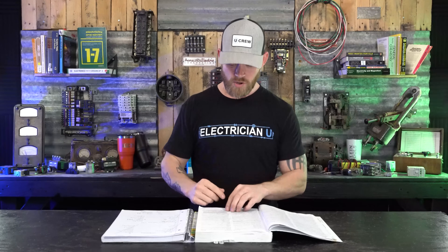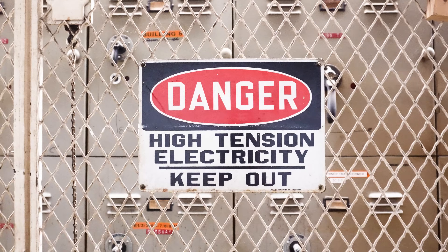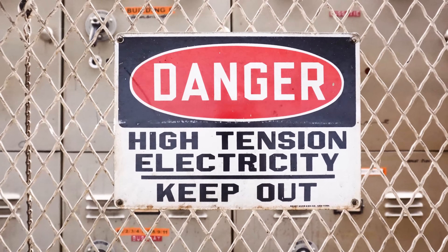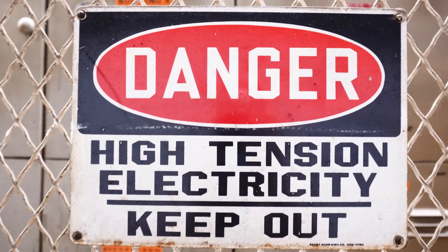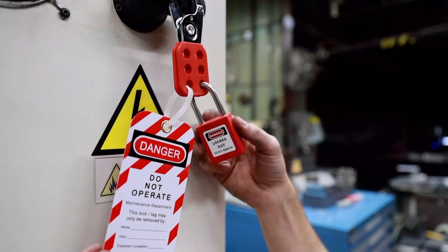Next up is 'enclosed.' There's a difference between concealed and enclosed, and this is where the confusion comes in. Enclosed means surrounded by a case, housing, fence, or walls that prevent a person from accidentally contacting energized parts. It might be an area of electrical equipment someone can't enter, or it might be an enclosure like a box with a cover that you could put a lock on — something that prevents people from touching live parts inside a panel, for example.